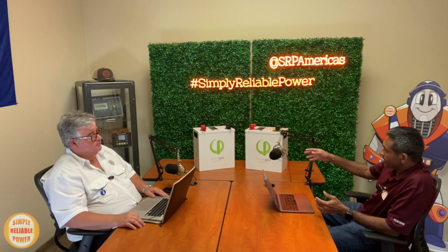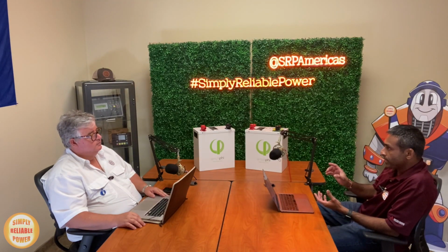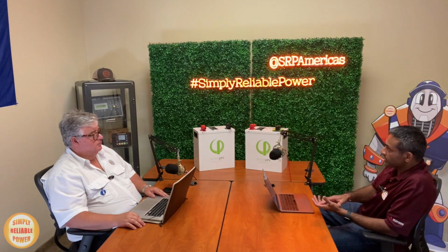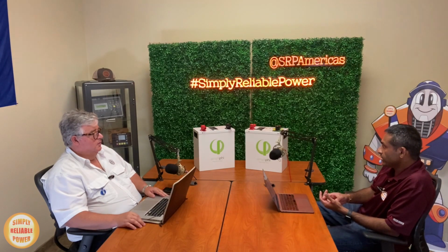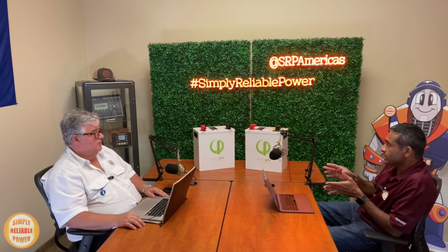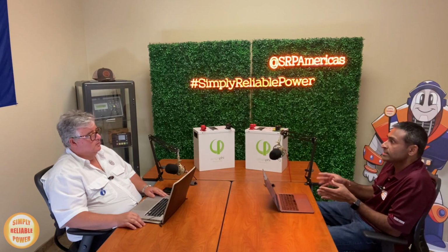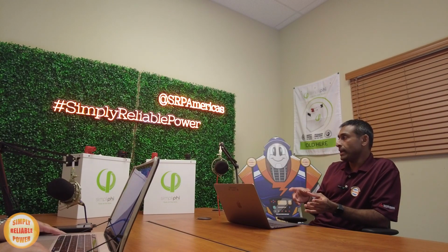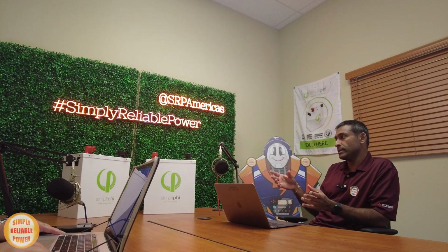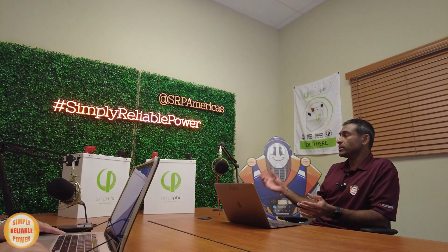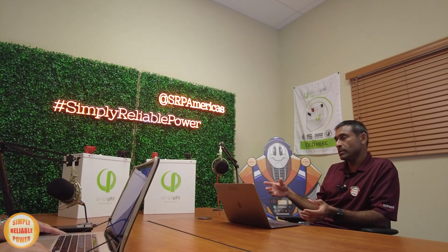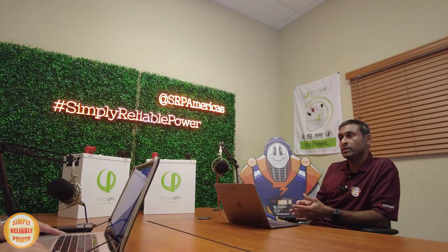The PHI battery has a simpler BMS that looks after the cells of that battery module itself. Just as background, each of these batteries has a lot of small battery cells, LFP cells, in series and in parallel to get the 51 volts and 3.8 kilowatt hours. So the PHI BMS looks after the individual cells in that battery. It measures the voltage to make sure that the cells are balanced and the safety of that individual battery. The AMPLIPHI battery has a more advanced BMS and more sensors, so it measures temperature as well as cell voltage, and therefore you can optimize the usage of the power on that battery, and it also communicates with other batteries that you have in parallel, plus an inverter that is compatible for closed loop communications.